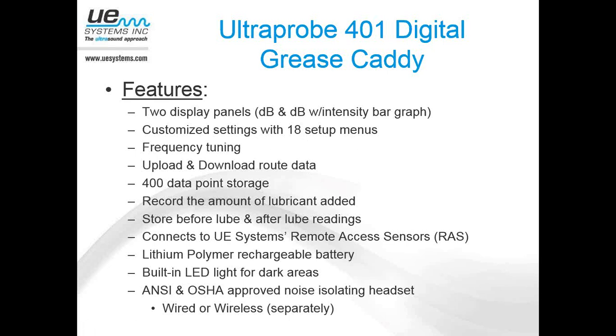One of the major differences between the Ultraprobe 401 and the Ultraprobe 201 that most of you are probably familiar with is the frequency tuning. The Ultraprobe 201 is on a fixed frequency, whereas with the Ultraprobe 401 we now have the ability to adjust the frequency just like any of our other Ultraprobes that have frequency tuning. So that's a big feature.